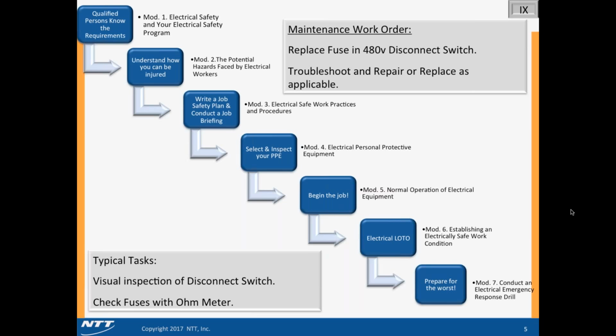We talk about how we properly verify - that's part of the hands-on procedure we do, making sure everybody understands how to properly verify. You check your meter, you check the circuit is de-energized phase to phase and phase to ground, and you recheck the meter when you're done. We talk about those steps that confirm we are in an electrically safe work condition, and that's our number one goal from an electrical standpoint.